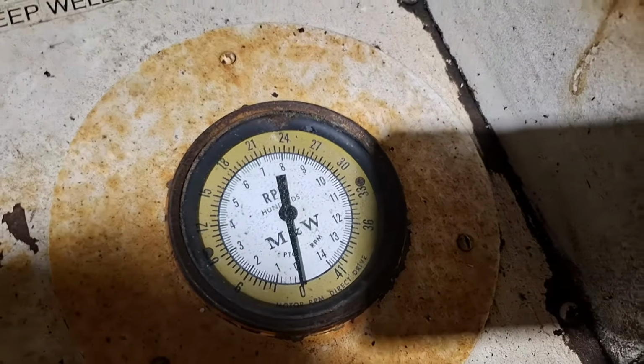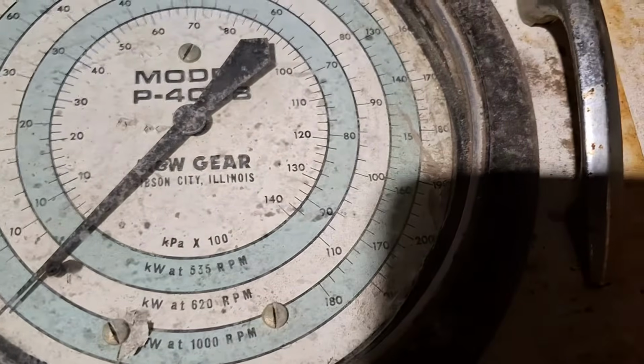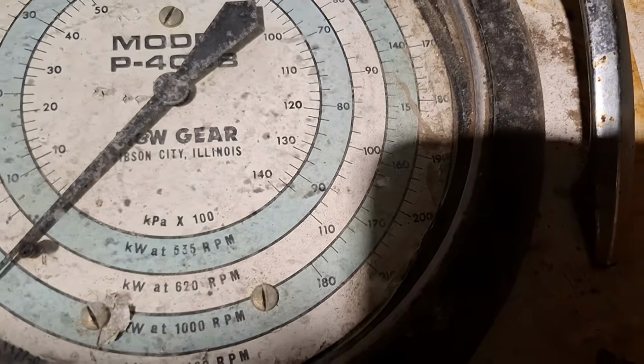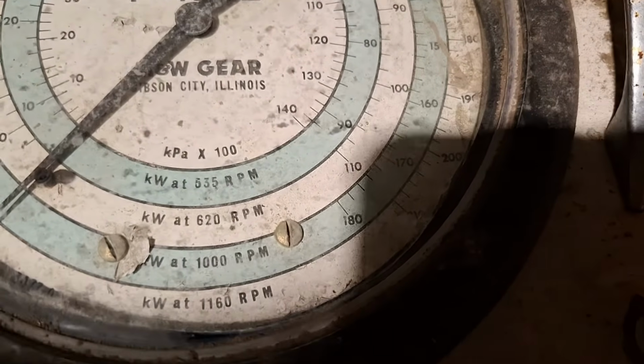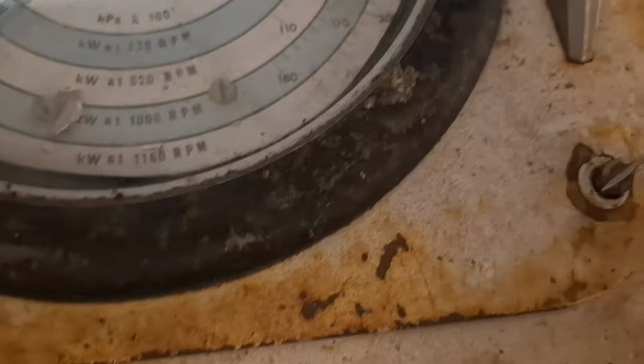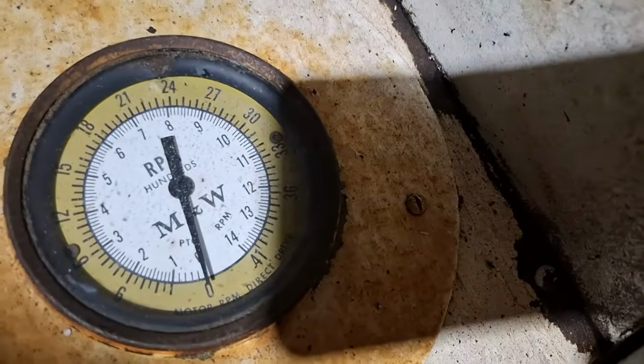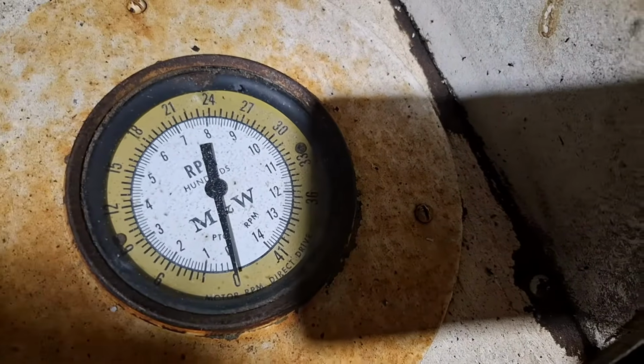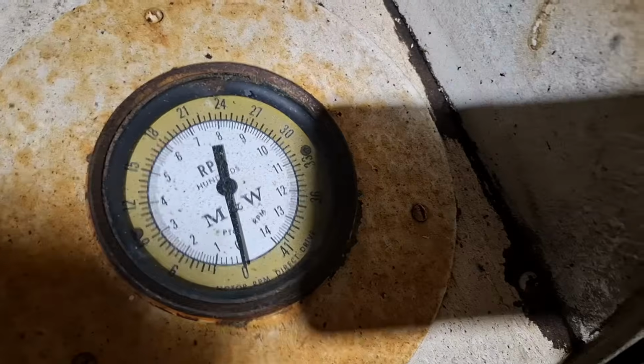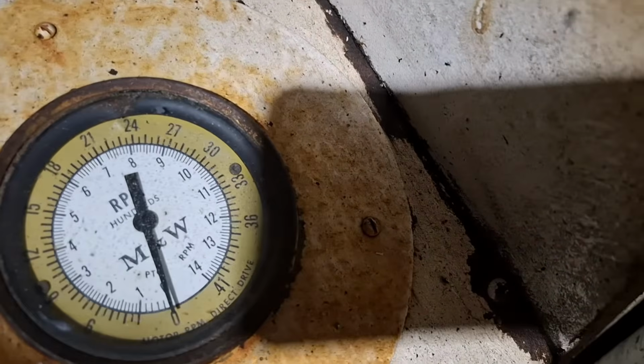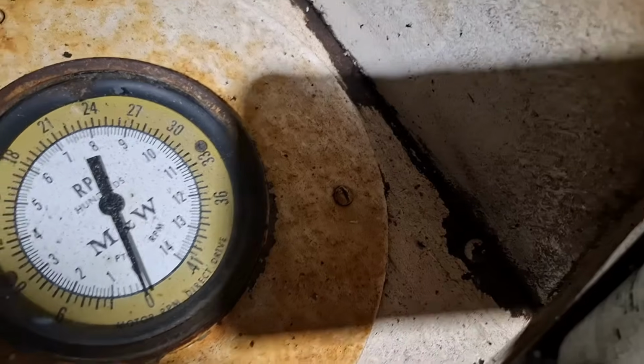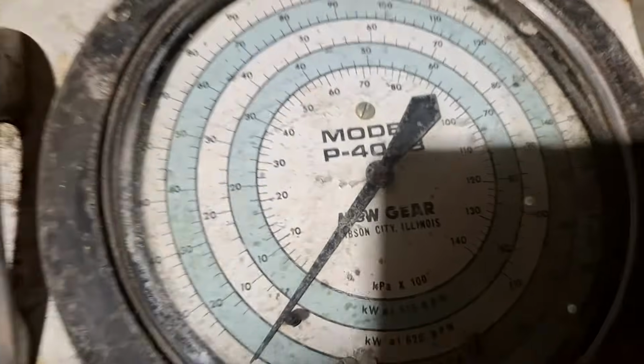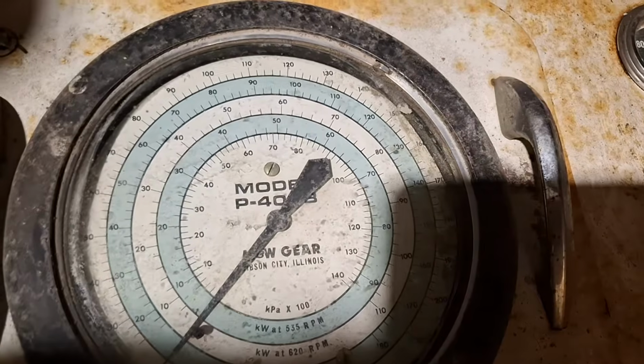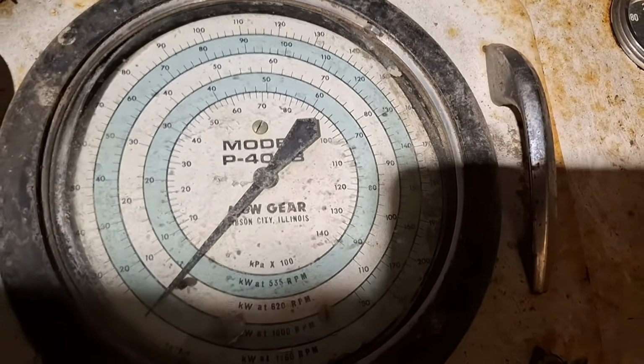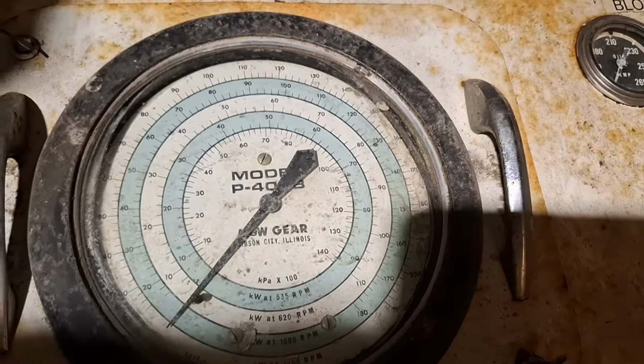So when you're running something up, you'd look at that gauge and get your speed, and then you have to bring it down to one of these ranges. So you can basically say your RPM was at 535, 620, 1000, or 1160. I think that's indicated on that gauge there. One of the white marks is actually missing. You've got 535, 620, up at 1000 there, and then 1160. So you make sure you're running at one of those speeds, and then what the dial runs up to, that's your kilowatt rating, because we're in kilowatts here, of what the tractor's outputting at that particular time.